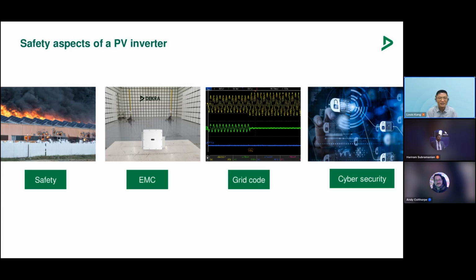Later, we started to find that EMC, electromagnetic compatibility, will also affect our life significantly. What is the risk if an inverter is not in compliance with EMC requirements? An inverter can interfere with the normal work of nearby equipment when it emits high radiation. The high radiation may also harm human health due to biochemical reaction in the human body coming from tiny current flowing in the body. Grid code is another important thing we should pay attention to.